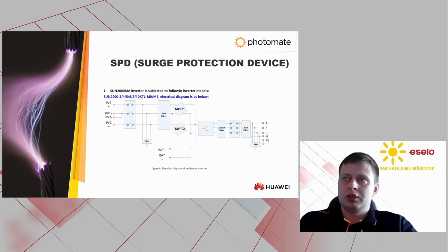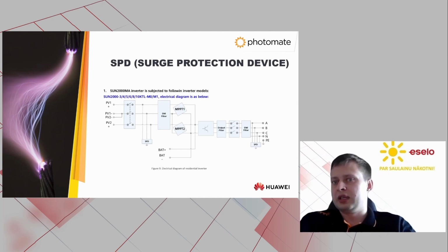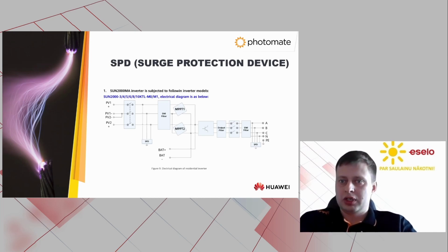A very common question is about SPDs in the inverter. SPD, surge protection device, plays a critical role in safeguarding the inverters and other electrical equipment from surges or electrical lightning, etc. The SPD provides a path for the surge current to go to earth, and this behavior saves the inverter from damage.